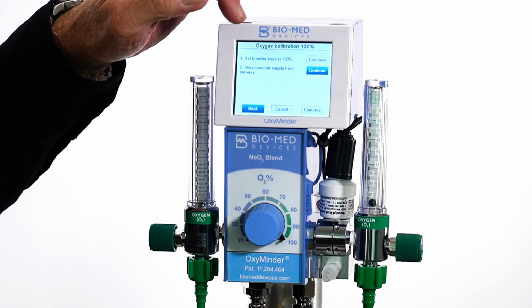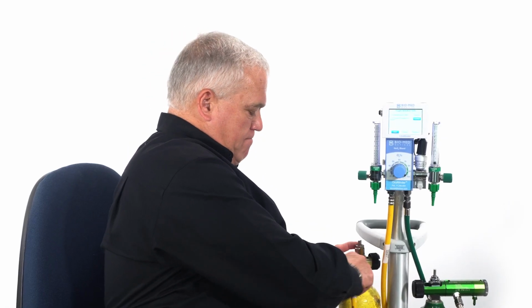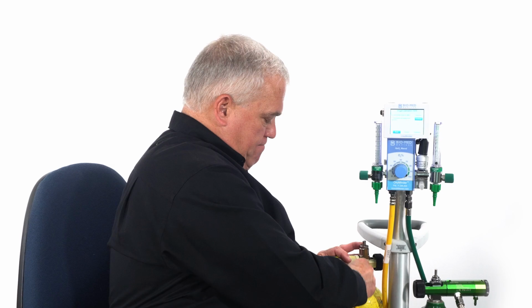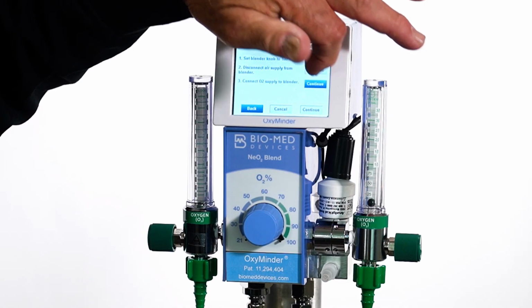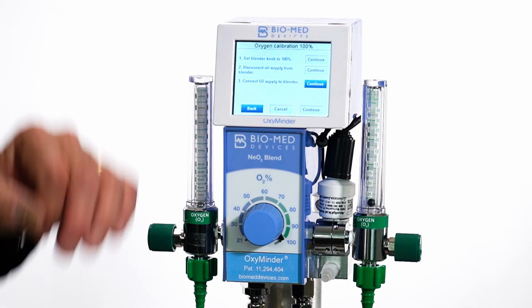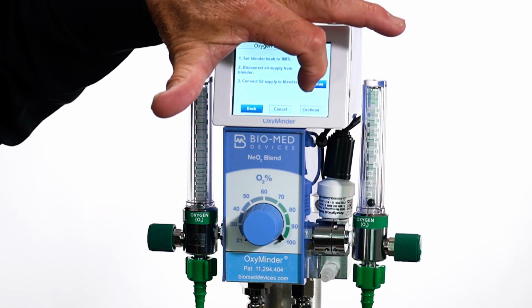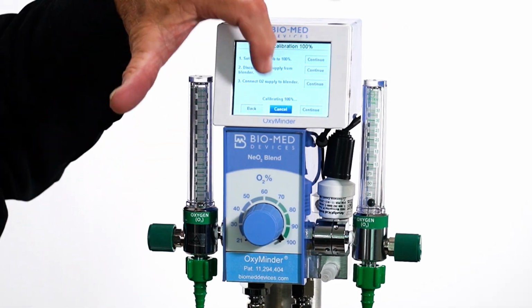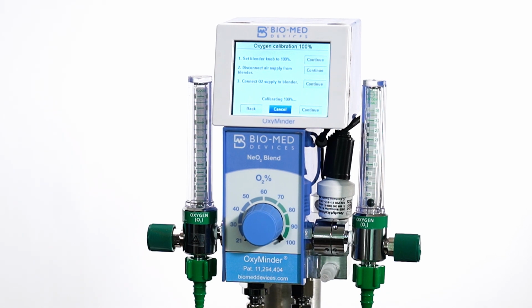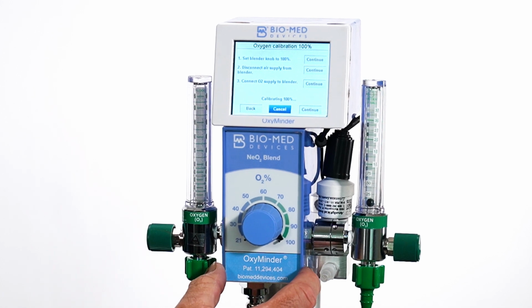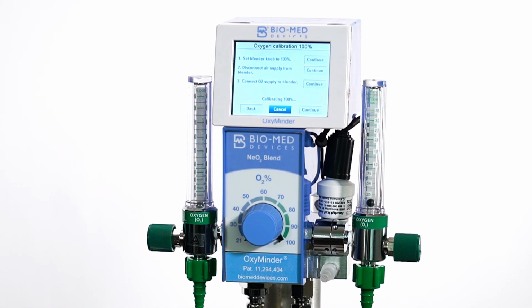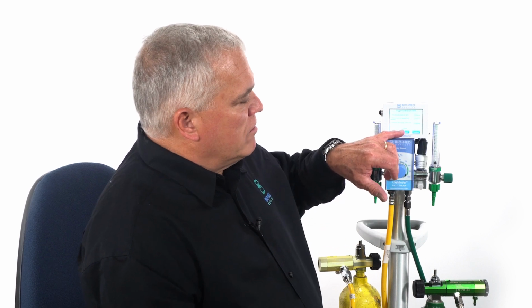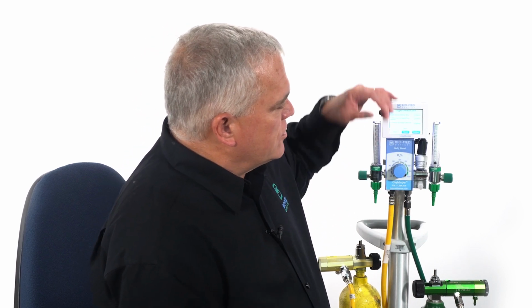Okay. So basically it tells us to set the blender to 100%, and I'm going to push continue. Disconnect the air supply. And continue. Connect O2 supply. I'm already connected, so I'll push continue, and now it's doing 100% cal. So basically what I've done is I'm supplying only 100% oxygen to the blender. I've disconnected the air supply so that I know that the sensor is only receiving 100%. So it came up to 100%, says done.